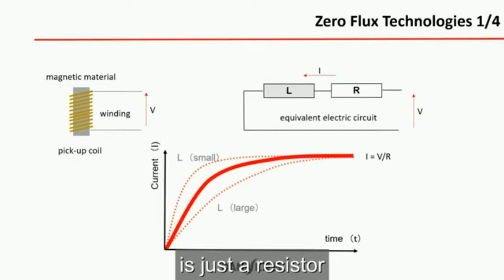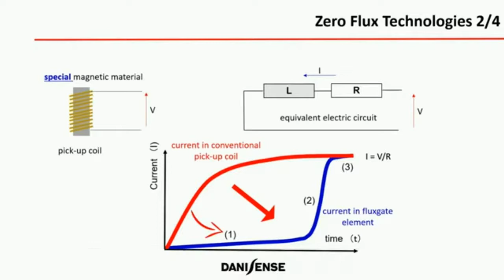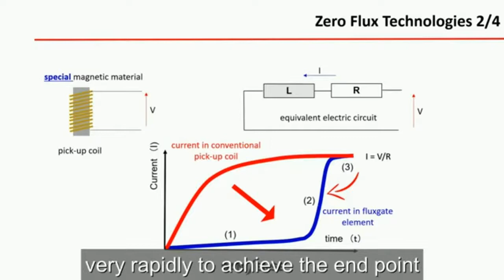In the case of the zero flux current transducer, the magnetic material used for the bar has specific magnetic properties, shown in the blue curve. At the beginning, the current grows slowly due to a high impedance value. Then, suddenly, the inductance saturates, and like a switch, the current increases very rapidly to reach the endpoint as before.